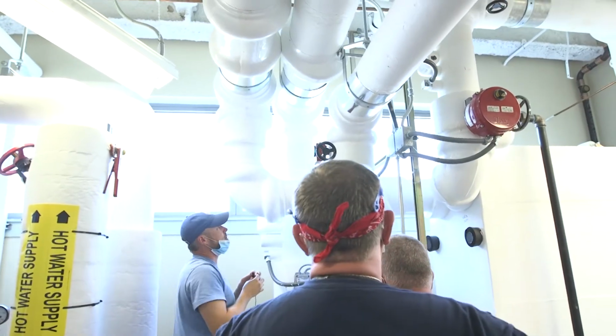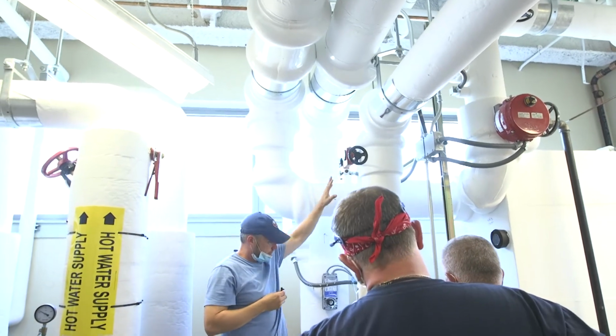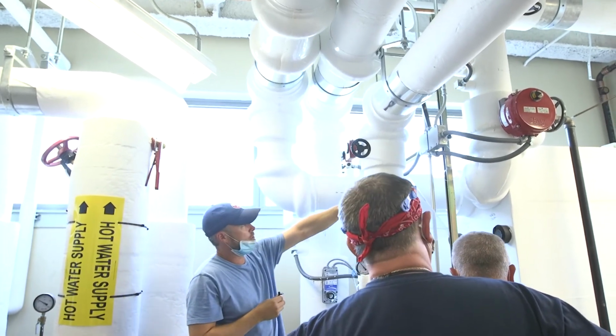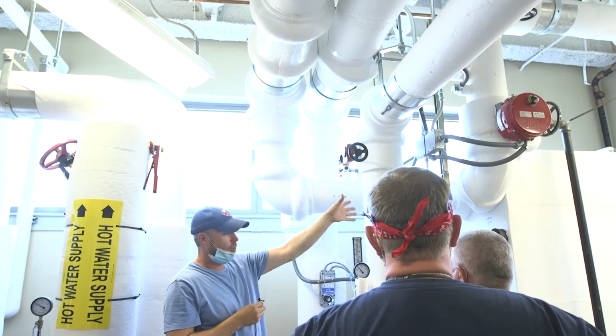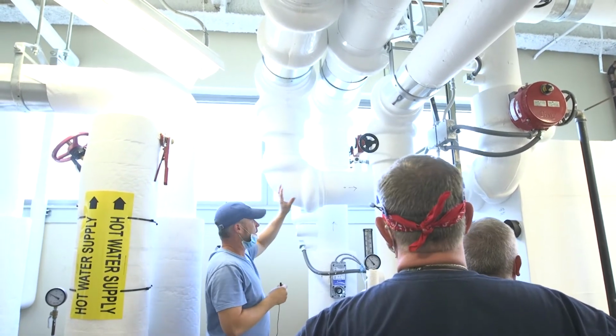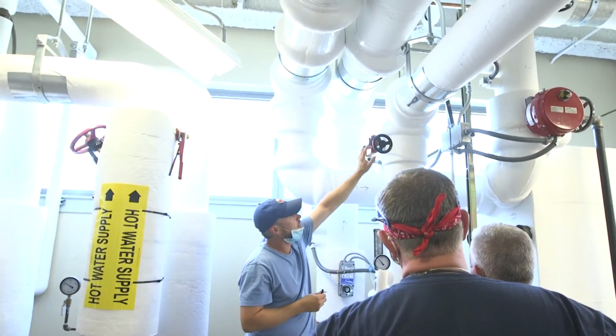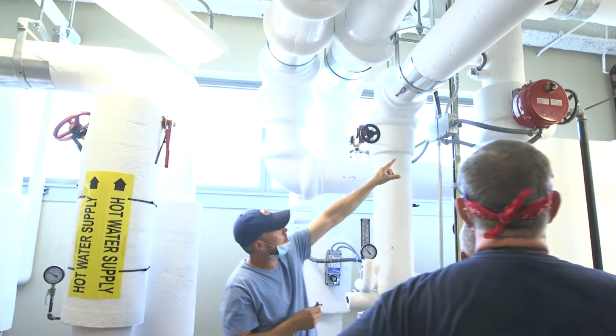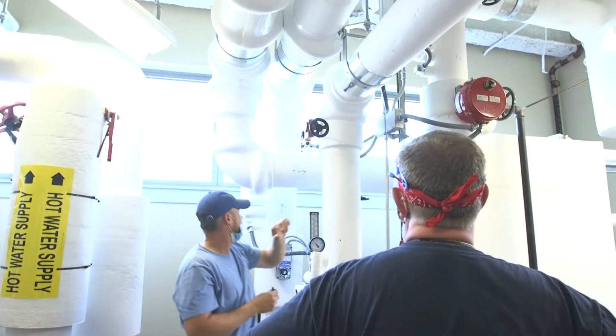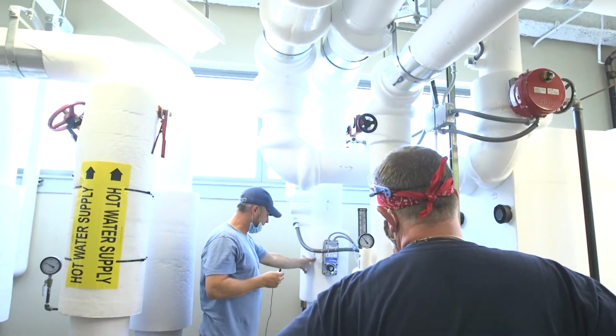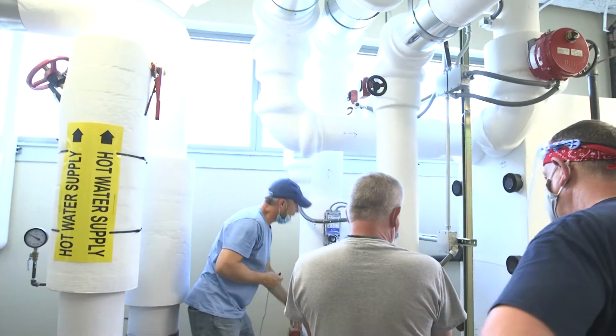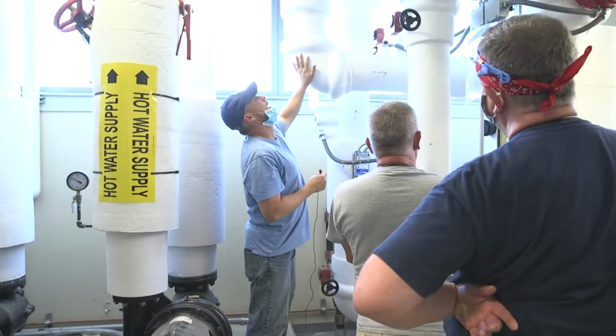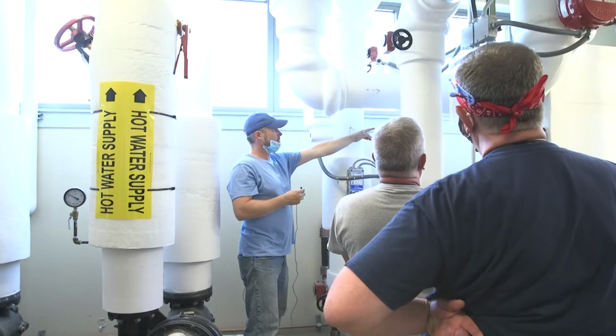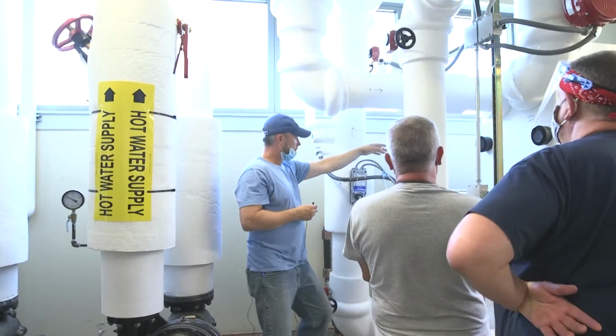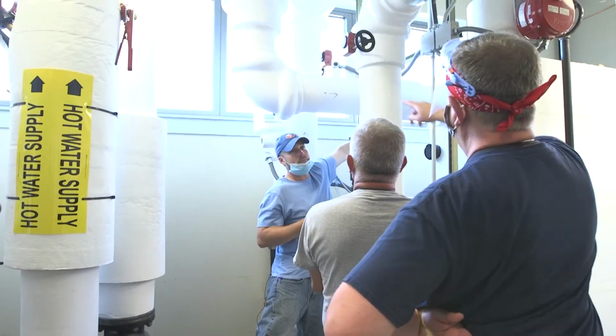These are just isolation valves. These are normally open valves. Your control valve is what's modulating the water temperature. So this is just isolation. That's modulation and isolation above it. And same thing on your plant side. You have isolation and isolation. So this right here, normally open.